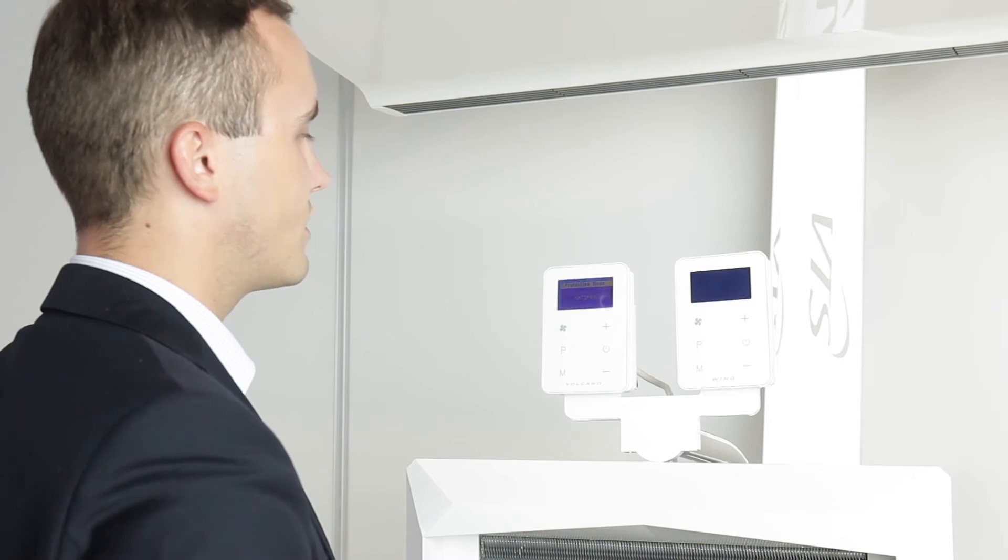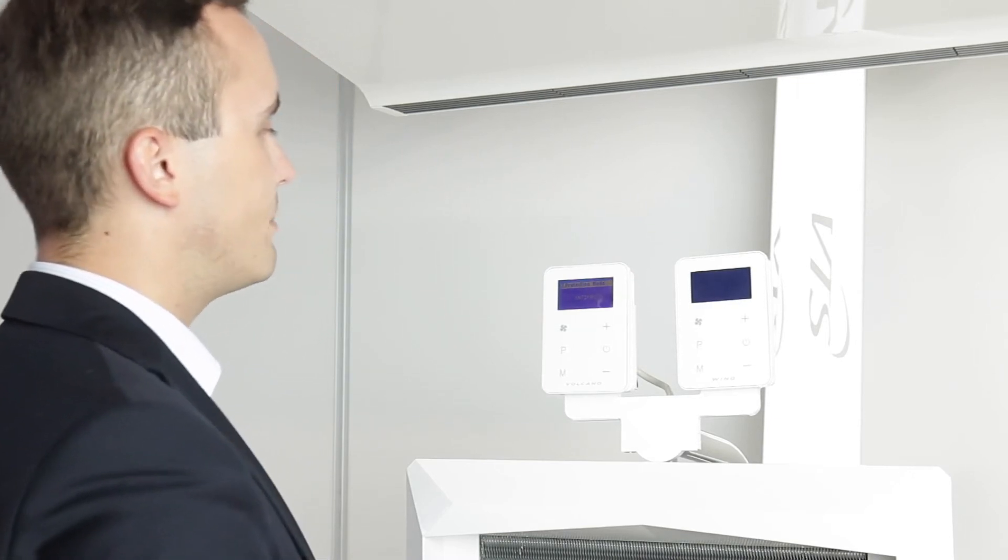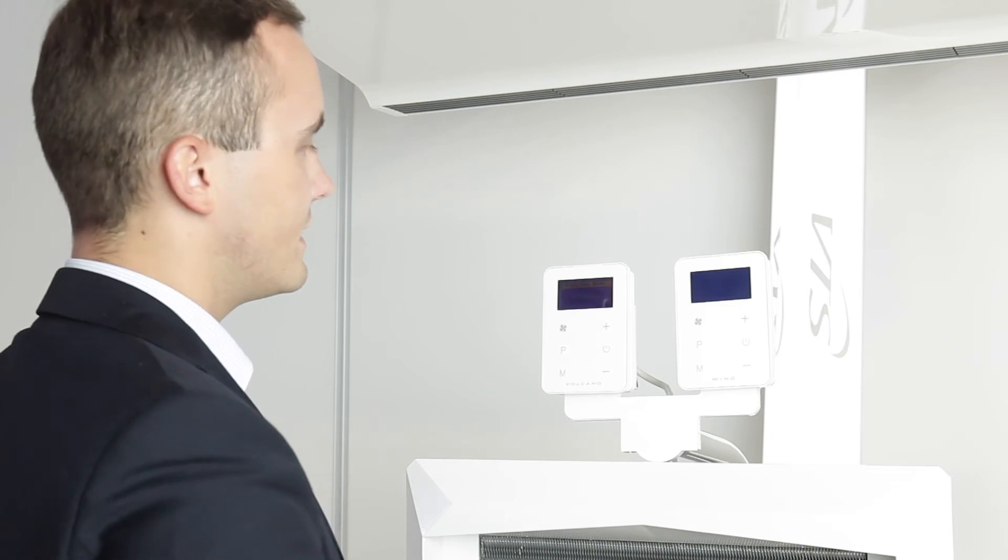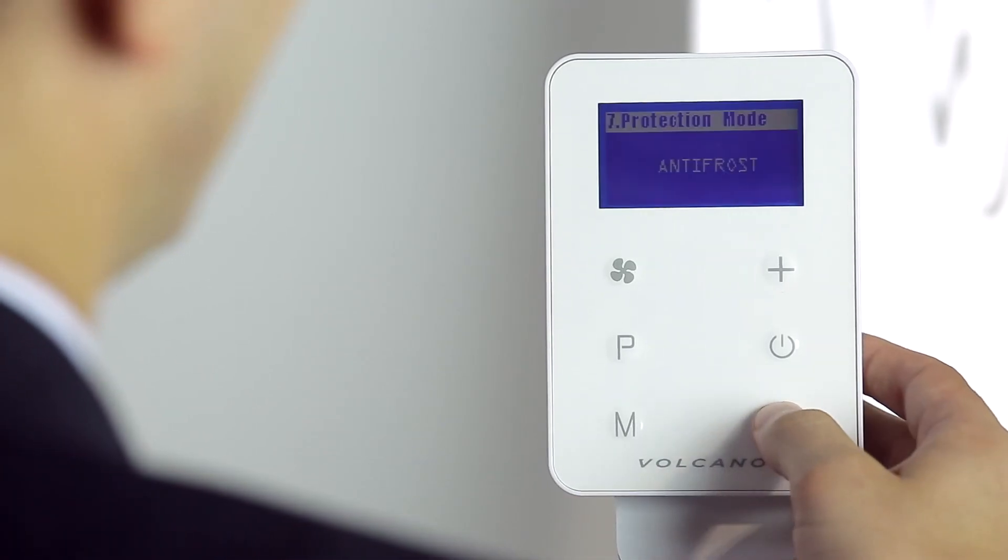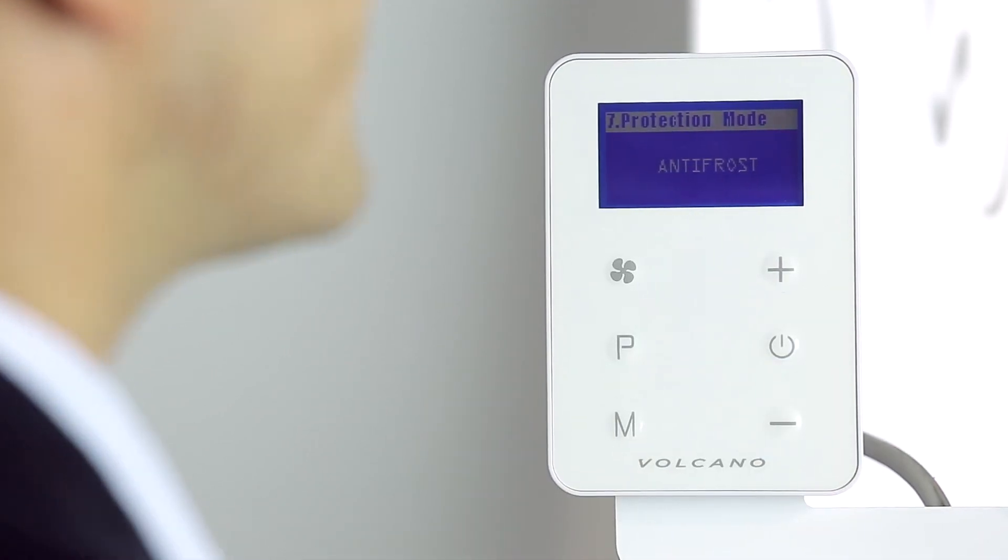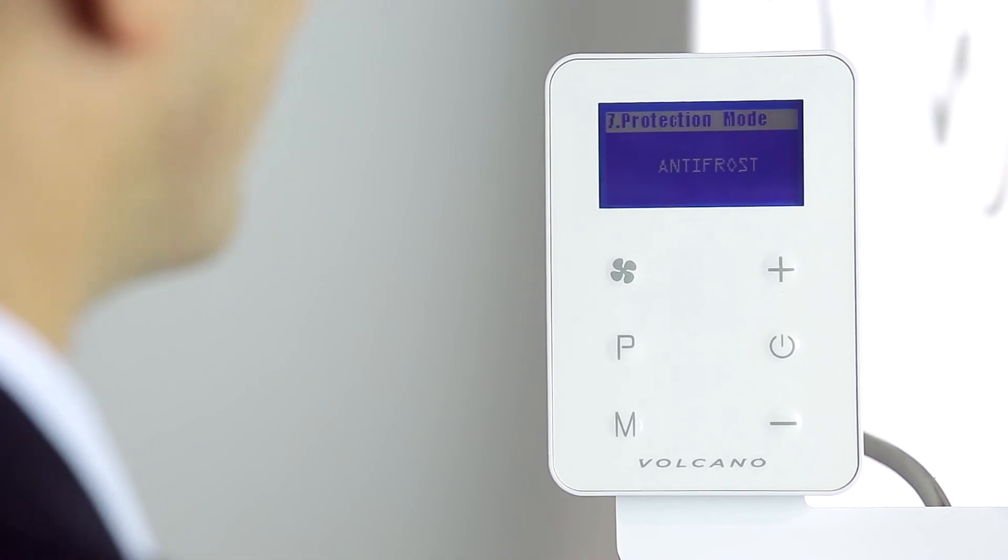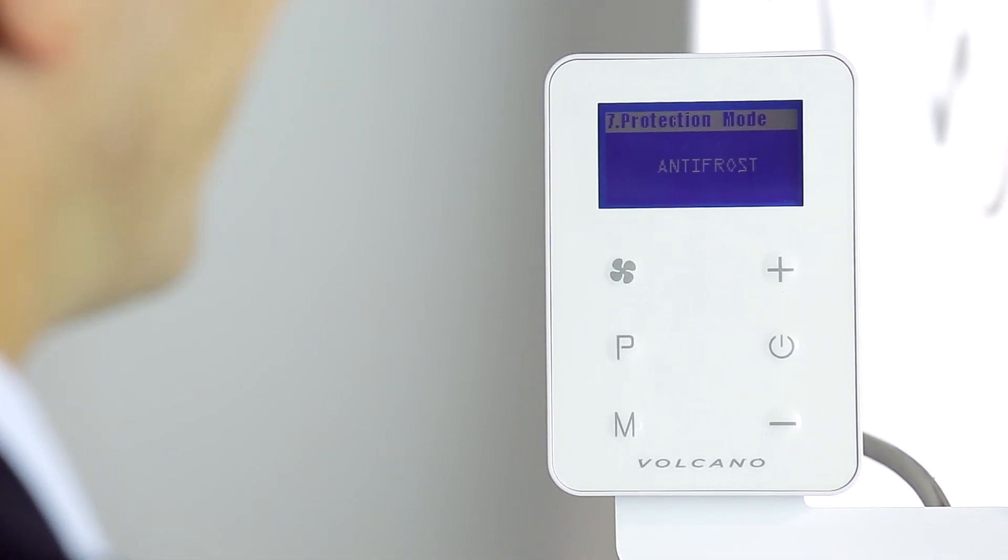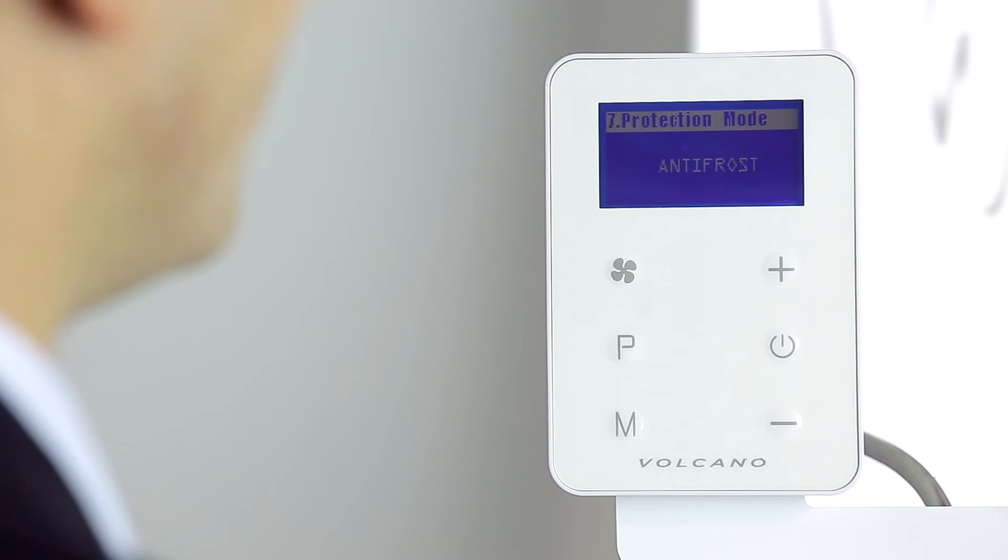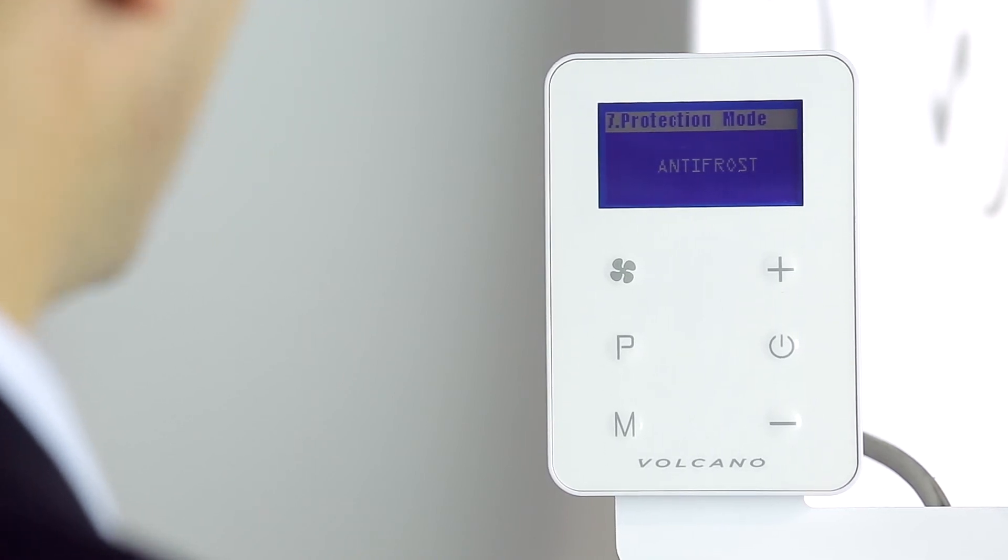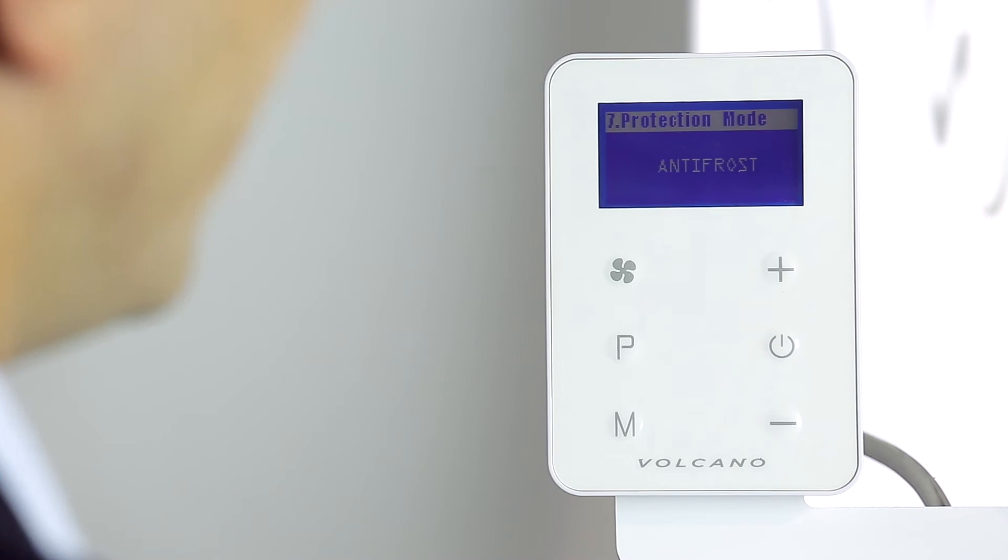Setting the anti-freeze temperature of the Volcano EC controller protects our heat exchanger from freezing. The temperature we have set in setting 6 will be the limit temperature. If the room temperature falls below this temperature, the two-way valve automatically opens and allows the heating agent to heat the exchanger and protect it from freezing.